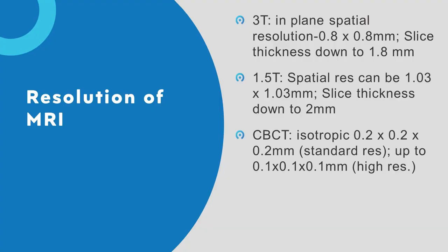Just briefly on resolution: on a 3T MRI, the in-plane resolution will be down to 0.8 mm — less on a 1.5T. But the cone beam standard resolution is 0.2 mm, and the high resolution is up to 0.1 mm — 100 microns. So we get sharper images. From the resolution point of view, it's hard to beat. Contrast plus better resolution should be a winning combination.